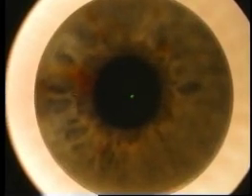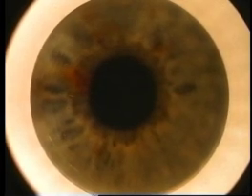Instead of using planar applanation, it uses a curved contact glass. The advantage of this is that you can create flaps without really increasing the intraocular pressure very much, meaning that during the procedure, patients really do retain vision throughout. Because of the curved contact glass, and because the patient is able to self-center their eye on the fixation target, and because the contact lens and the fixation target are coaxial, this system auto-centrates itself — auto-centrating the flap on the corneal vertex or visual axis, which is exactly where you want it, since ablations should be centered on the visual axis.